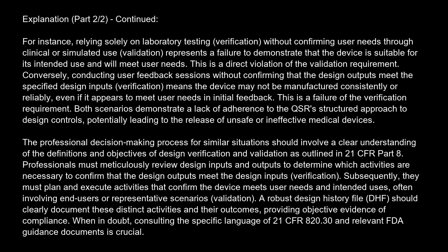Subsequently, they must plan and execute activities that confirm the device meets user needs and intended uses, often involving end users or representative scenarios (validation). A robust design history file, DHF, should clearly document these distinct activities and their outcomes, providing objective evidence of compliance. When in doubt, consulting the specific language of 21 CFR 820.30 and relevant FDA guidance documents is crucial.